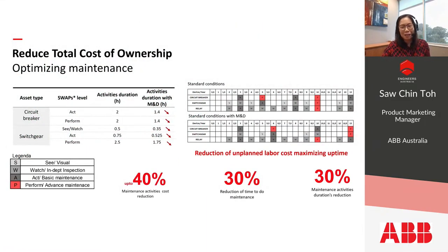Condition monitoring doesn't mean that the system is maintenance free. It is there to optimize the whole process of maintenance. The two tables shown on the right-hand side of the chart are the comparison between the standard and the condition-based maintenance for switchgear, including its key components, for example, the circuit breakers, the panel itself, and also the protection relays which are installed inside the panels.